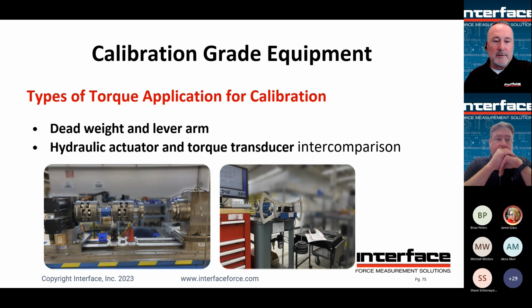The image on the right: we've got a calibrated or certified lever arm and calibrated or certified weights, and we can generate known torques from the force times distance calculation. On the left would be a hydraulic actuated system, which can apply higher loads.